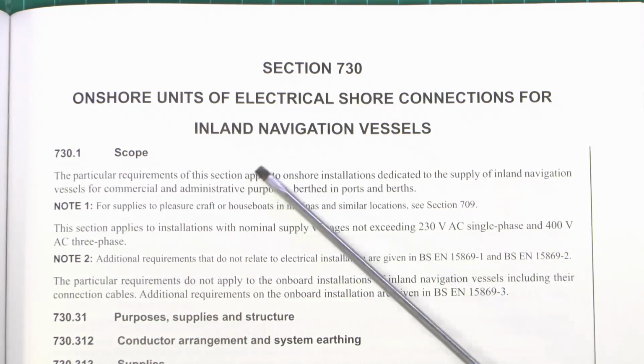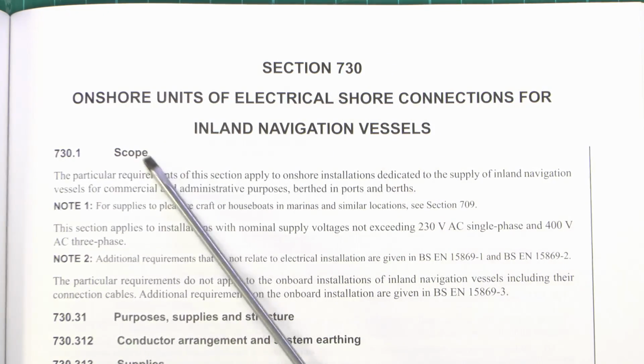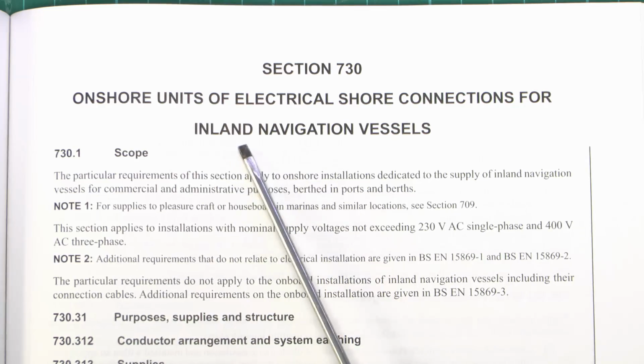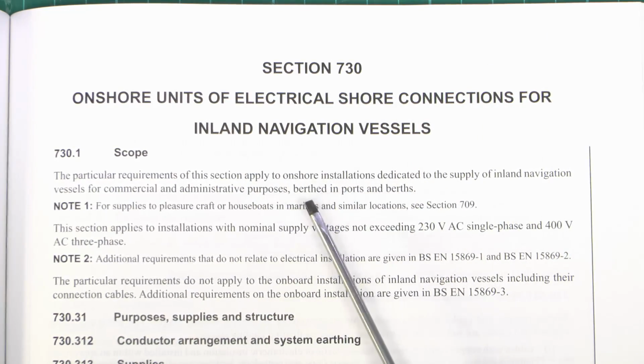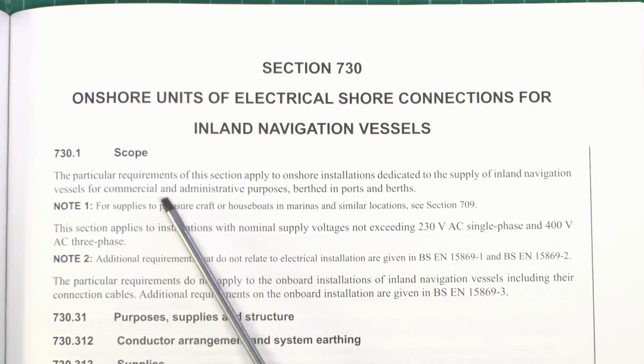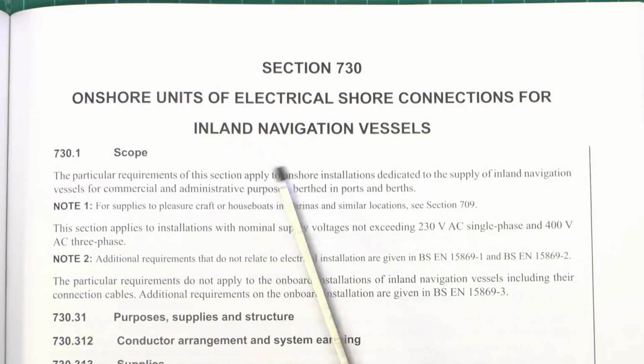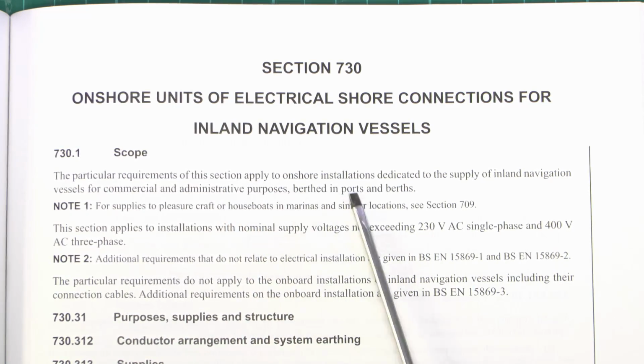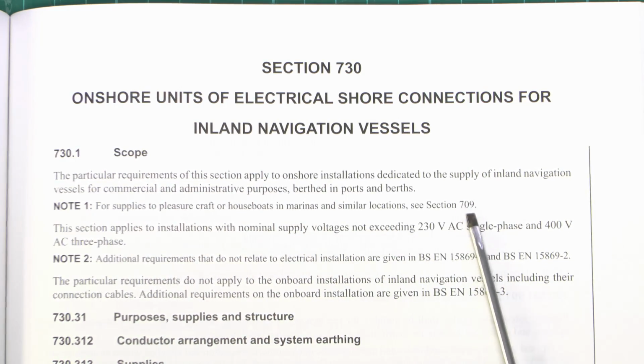Now section 730 is actually a completely new one. This didn't exist before at all, and this is for onshore units of electrical shore connections for inland navigation vessels. And this is in a similar kind of line to marinas, in that what we're covering here is the equipment that's located on the shore where you would connect to your inland navigation vessel when it was actually in there. And as I said here, the particular requirements of this section apply to onshore installations dedicated to the supply of inland navigation vessels for commercial and administrative purposes, berthing in ports and berths. And it does also refer to the marina section, which is of course 709, which we've seen before. So this part is entirely new, although a lot of it is based on what's in the marina section. It's now just putting it in a specific section for these types of vessels.